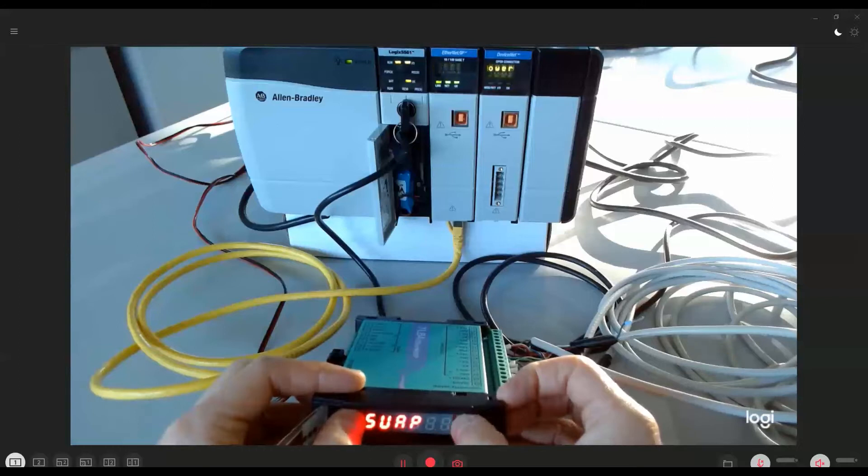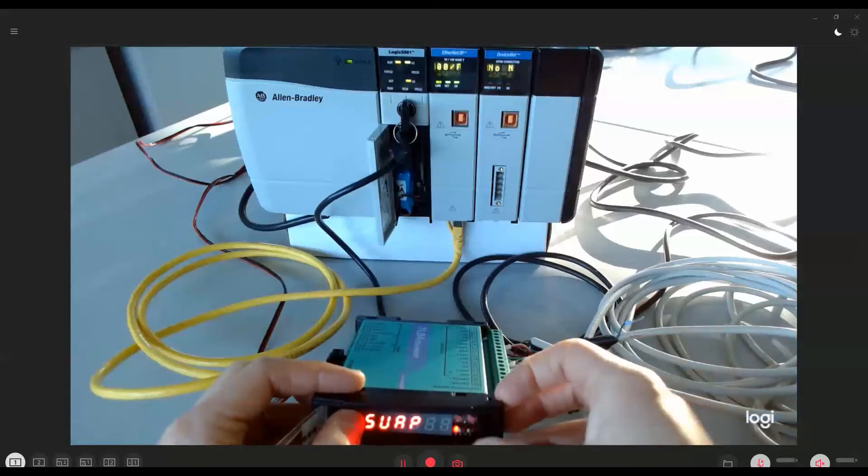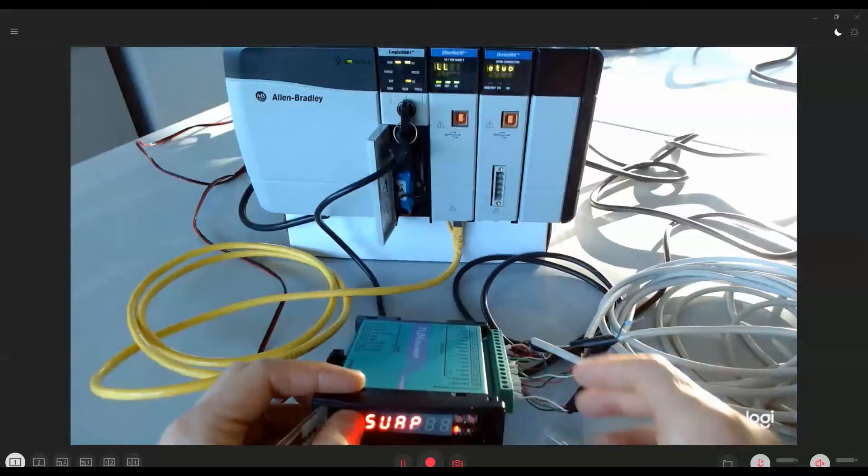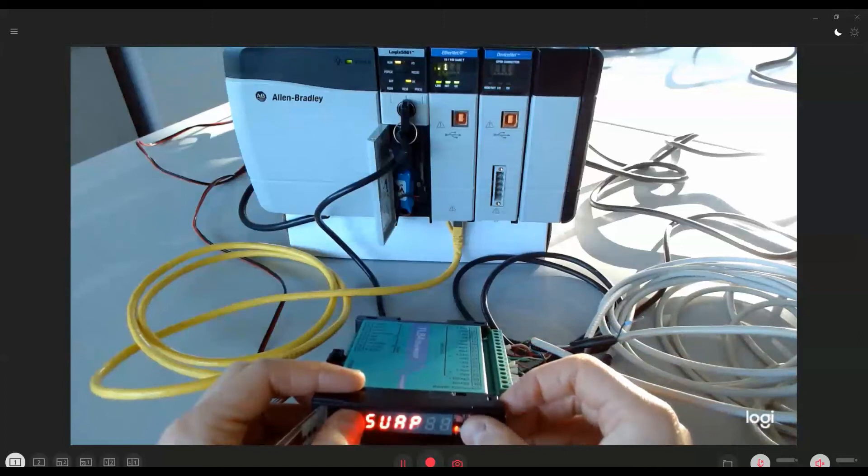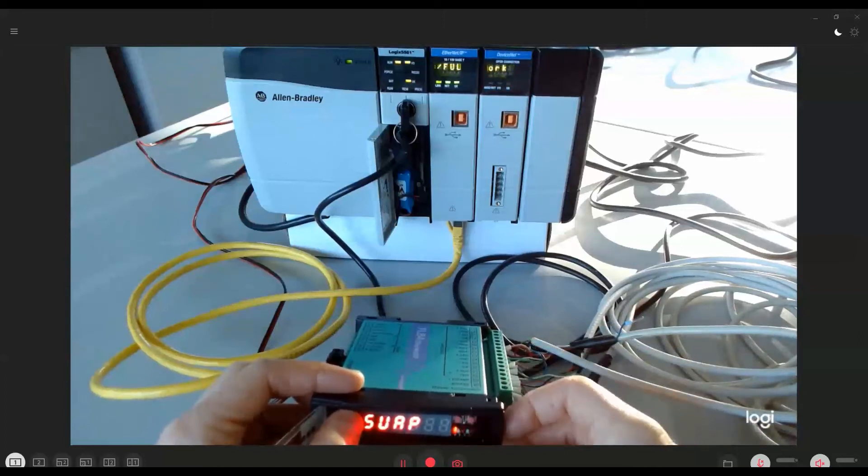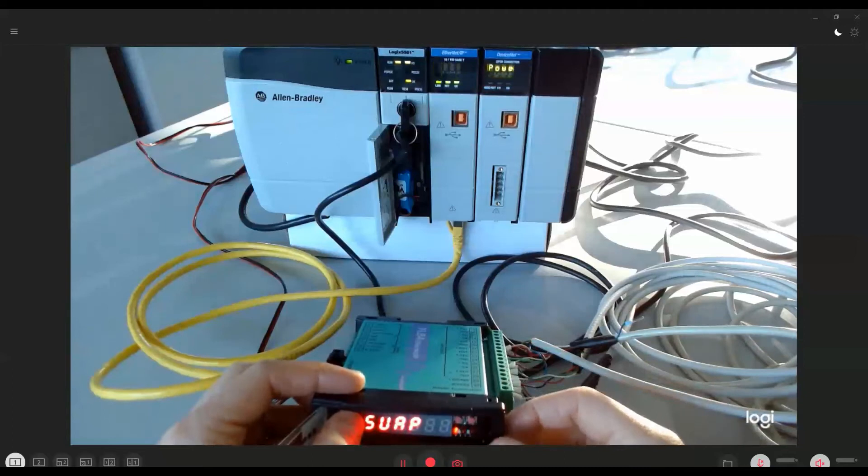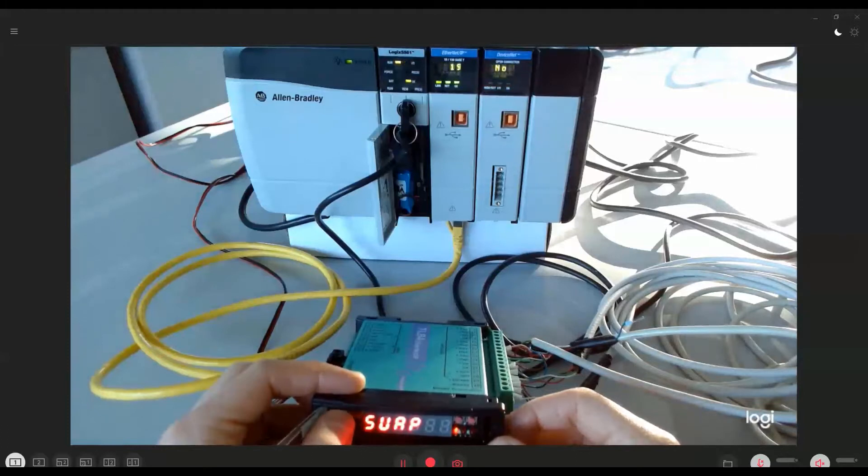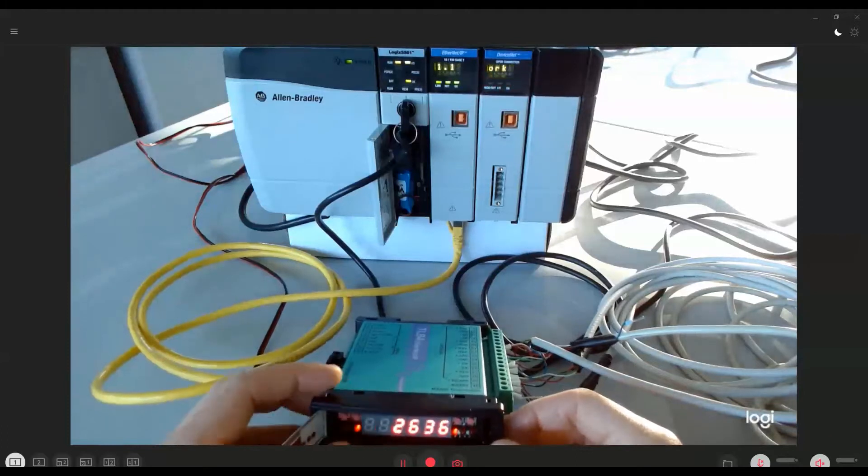The swap parameter defines the byte order used for the data exchanged on the Ethernet IP bus. The default value is kept at NO, corresponding to the Little Endian notation. Some more details about this parameter will be given later in this tutorial. Now we can move on to the RSLogix 5000 interface.